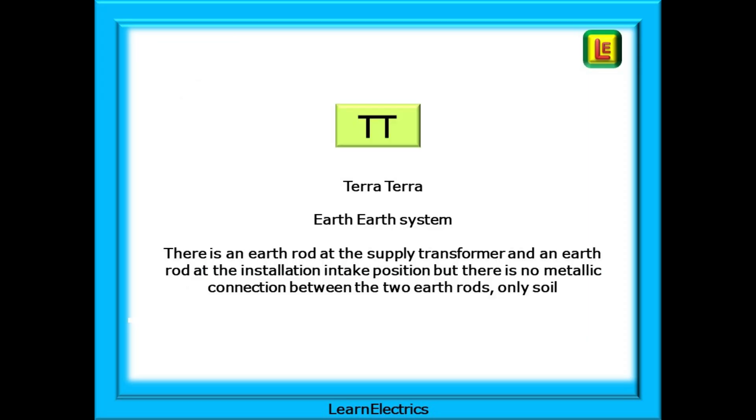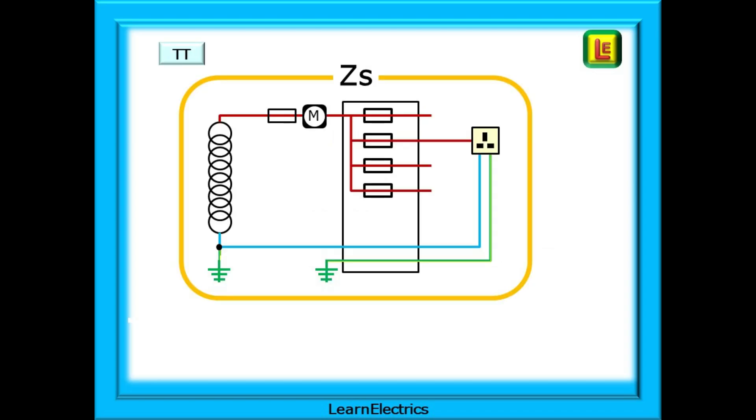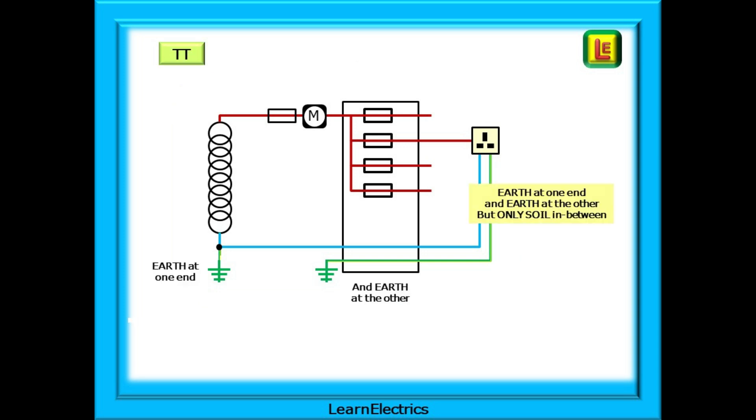The third type of system that we should look at is the TT system. Terra-Terra, or Earth-Earth system. There is an Earth Rod at the supply transformer, and an Earth Rod at the installation intake position, but there is no metallic connection between the two Earth Rods. Only soil. And these Earth Rods can sometimes be hundreds of metres apart. TT is a very much older earthing system, but there are still plenty of them all around the country, and indeed, TT systems are still installed in some locations. Don't think that TT systems are just used in the countryside. Where I used to live, hundreds, possibly thousands of houses in the town centre are on a TT system. That's what was installed many, many years ago. The system still works. Why change it?